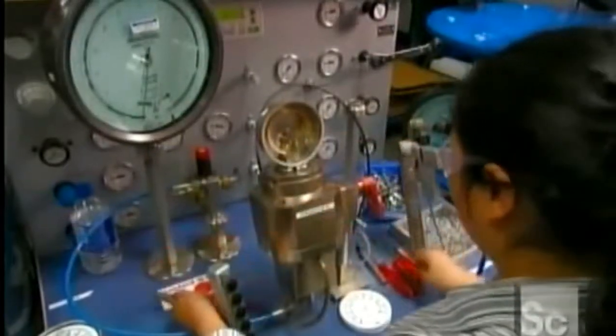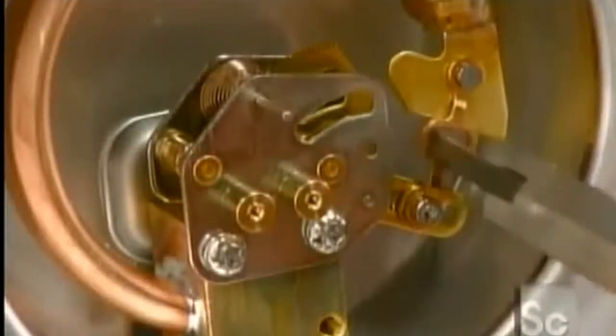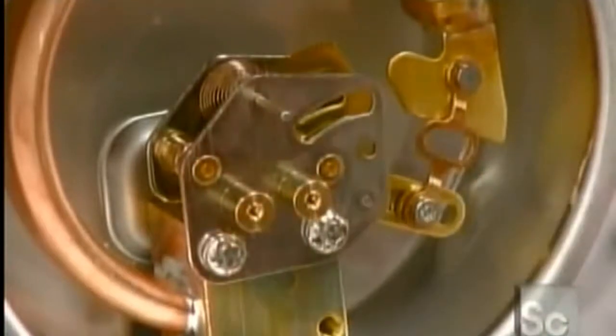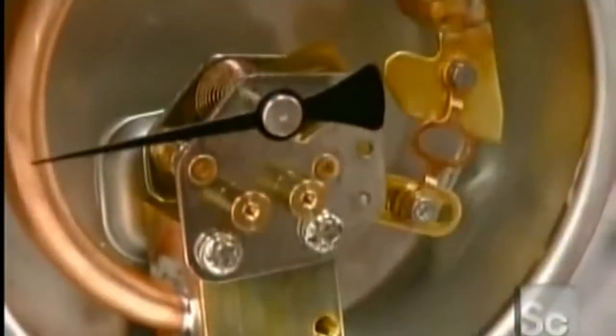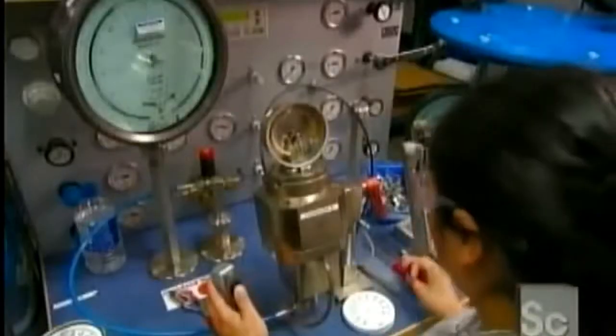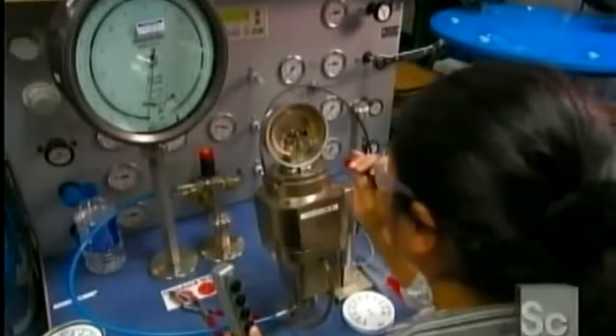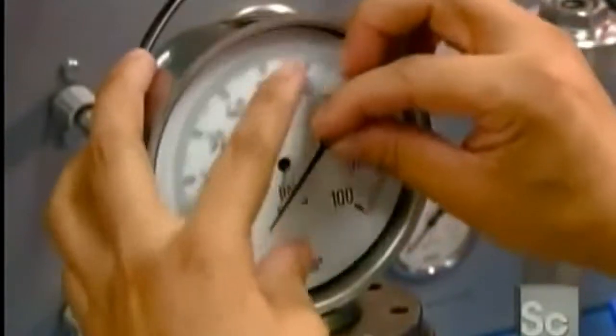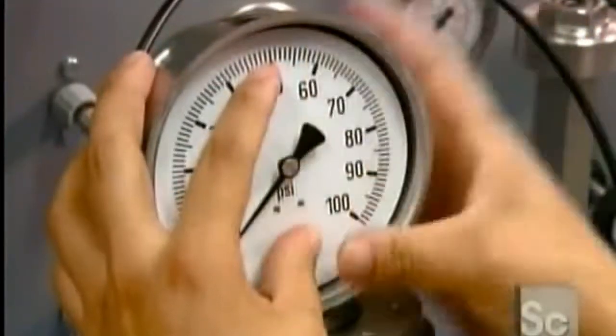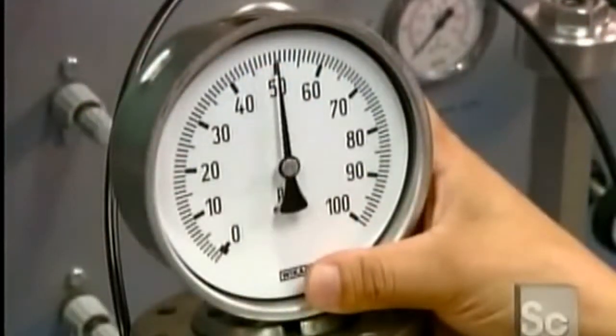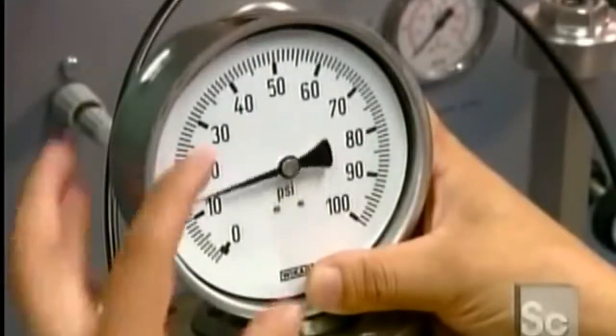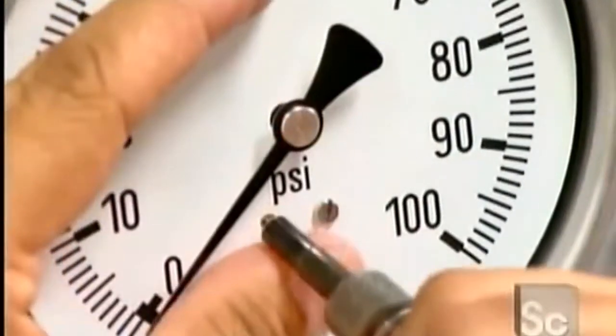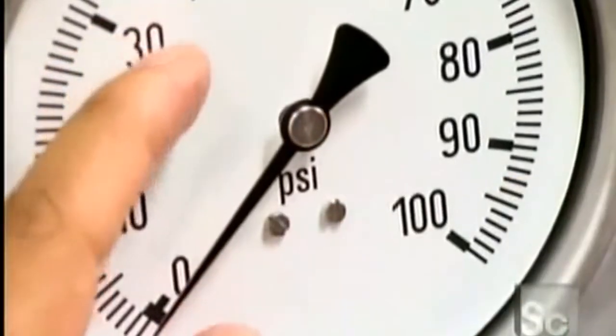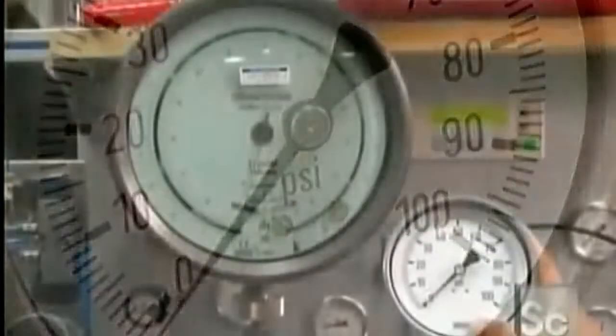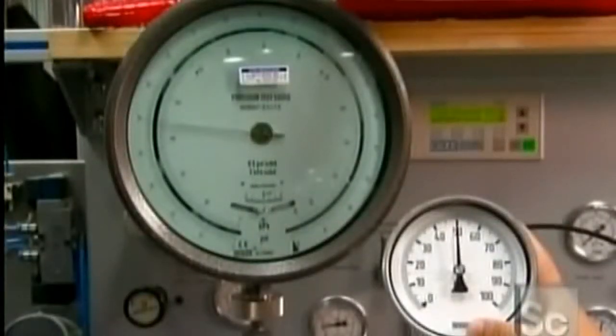Next, a worker calibrates the assembly. She loosens up the connecting links slightly to prevent friction, puts on the indicator needle, and runs a test. After a bit more adjusting, she puts the faceplate and the indicator needle back on. She ensures the gauge reads accurately at 3 key positions, and then screws the faceplate onto the gauge. A final test confirms it is calibrated properly.